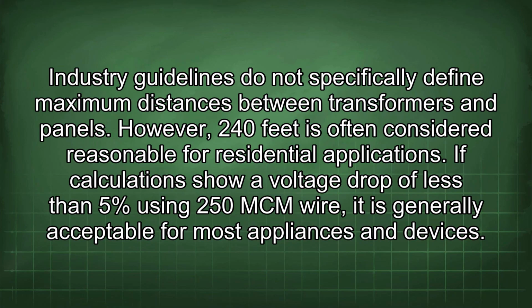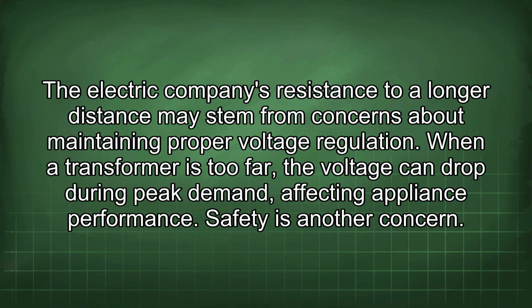Industry guidelines do not specifically define maximum distances between transformers and panels. However, 240 feet is often considered reasonable for residential applications. If calculations show a voltage drop of less than 5% using 250 mcm wire, it is generally acceptable for most appliances and devices. The electric company's resistance to a longer distance may stem from concerns about maintaining proper voltage regulation.